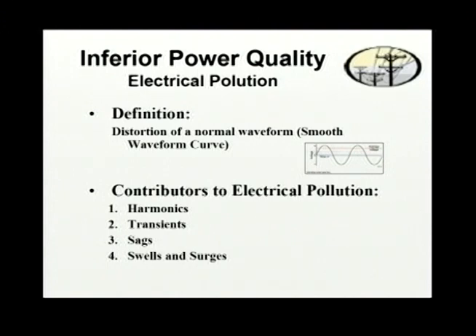Inferior quality power is distortion of the normal 60 Hz waveform and causes pollution of the electric supply. Harmonics are frequencies greater than 60 Hz. Transients are short duration voltage spikes. Sags are voltages 5% less than normal or nominal. Swells are voltages 5% more than normal, and surges are short-term high voltage transients. They all contribute to electrical pollution of the environment. Frequencies other than 60 Hz are called electrical noise.